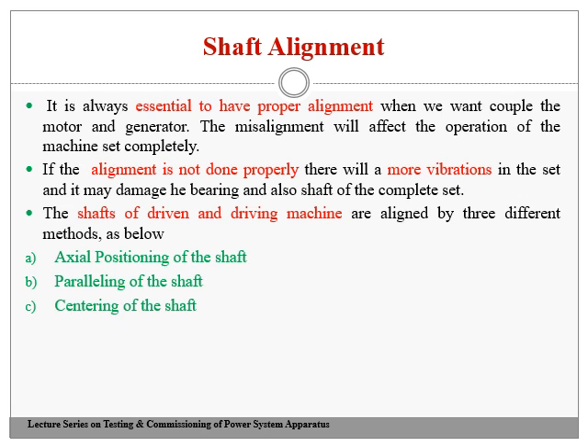It is always essential to have proper alignment when we want to couple the motor and the generator. Misalignment will affect the operation of the machine completely. There are a lot of complications if you do not properly align the motor and the generator. If the alignment is not done properly, there will be more vibrations in the set and it may damage the bearing and also the shaft of the motor completely. The bent structure of the motor comes into the picture whenever you don't align the motor and generator properly. Therefore, proper alignment is essential. The shafts of a driven and a driving machine are aligned by three different methods, available to couple the motor with a DC generator or AC generator. The three methods start with the axial positioning of the shaft.